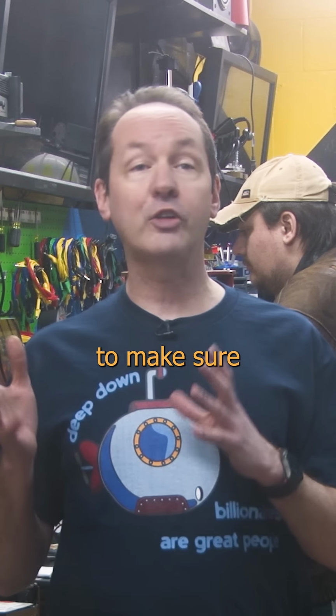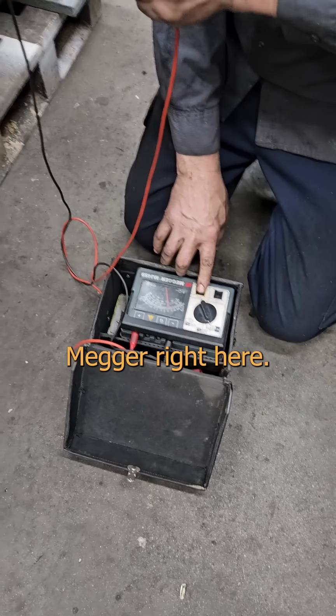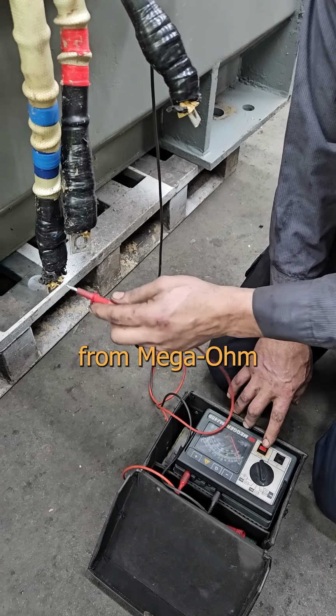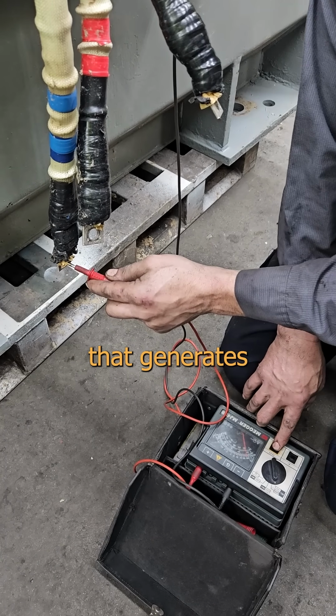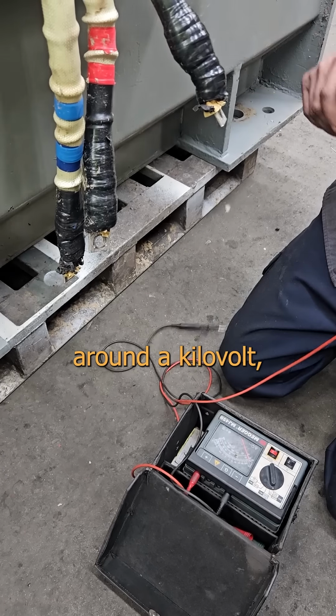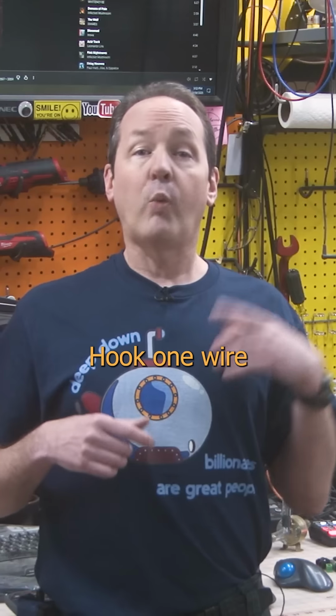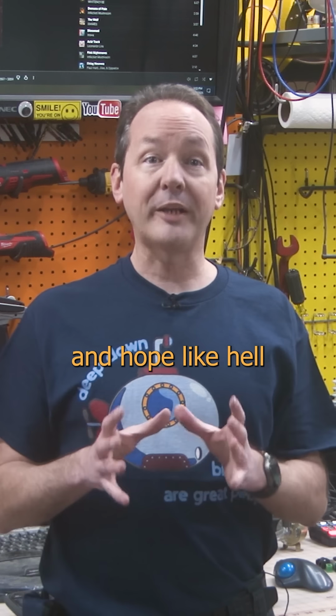So how do we test to make sure the wires don't fail? Check out this megger right here. The name comes from mega ohm meter, and it's a little torture box that generates a high DC voltage, around a kilovolt, and measures the resistance. Hook one wire to a winding and the other to ground, and hope like hell.